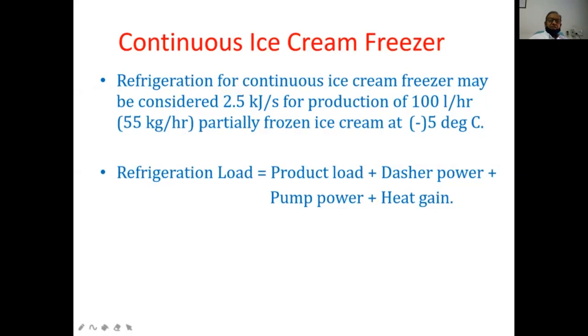But what is required? I will try to explain. We generally require 2.5 kilojoules per second for 100 liters, or say 55 kg per hour, of ice cream if it is partially frozen at minus 5 degrees centigrade. This we have practically studied, and we found that this is the minimum refrigerant requirement. Otherwise, the refrigerant load calculation requires product load, dasher power load, pump power load, and heat gain, and it requires detailed calculation for that.